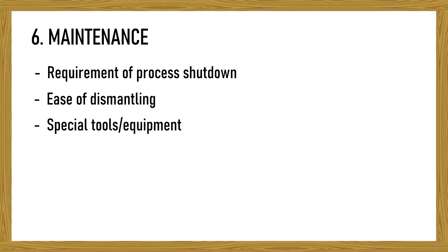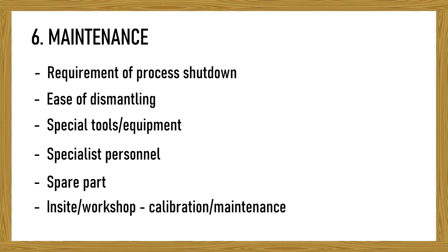Sixth, maintenance factor. There are several things which will impact maintenance process: requirement of process shutdown, ease of dismantling, special tools or equipment required, requirement of specialist personnel, availability of spare part, the capability of instrument to be calibrated in bench or vendor workshop. All these must also be considered when selecting the instrument.